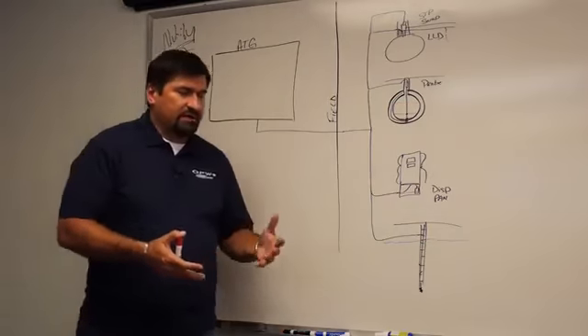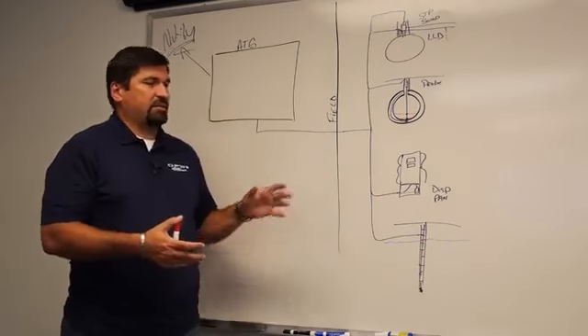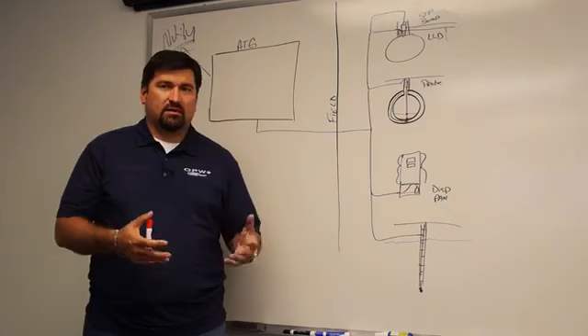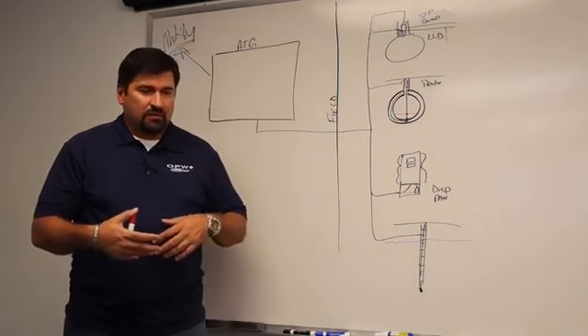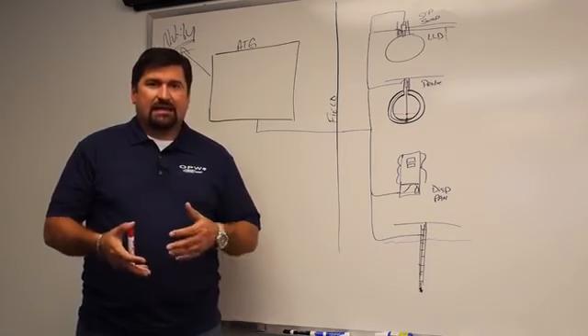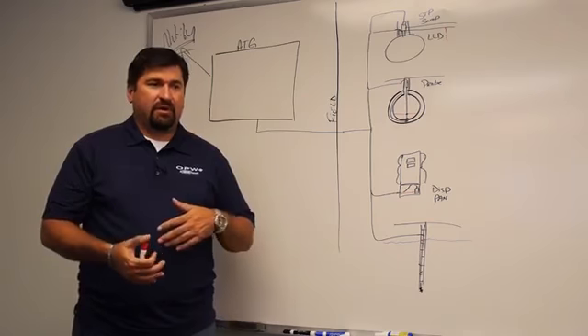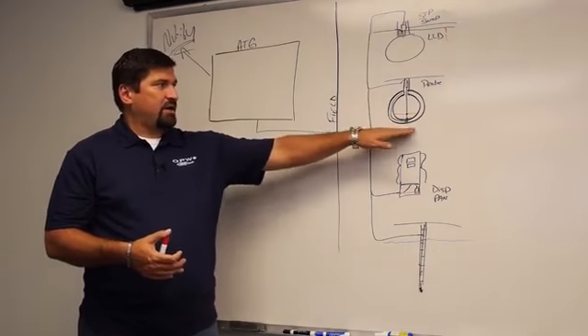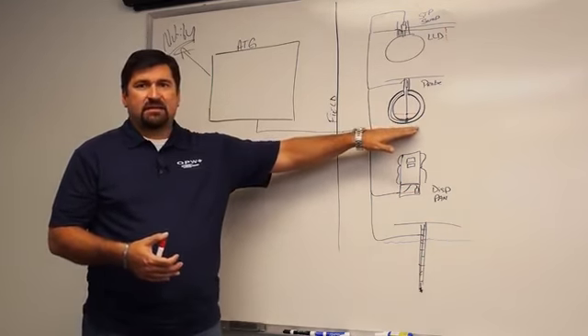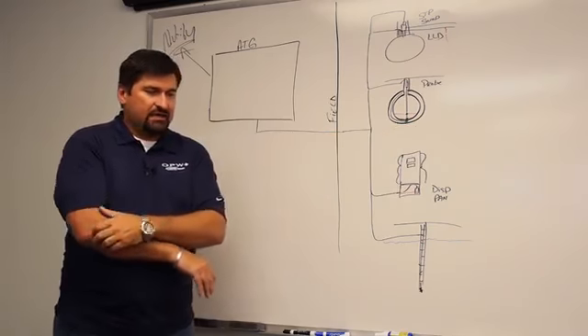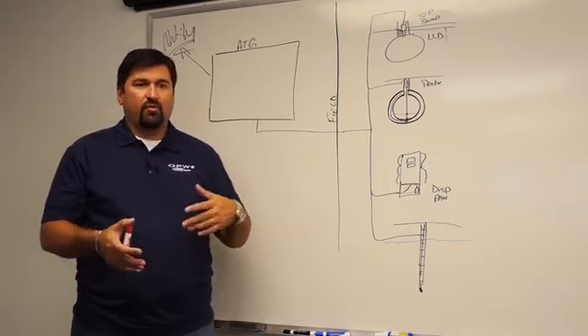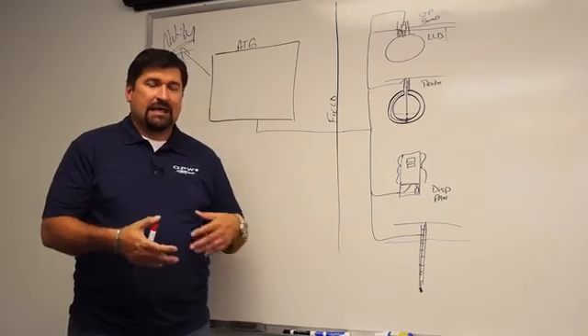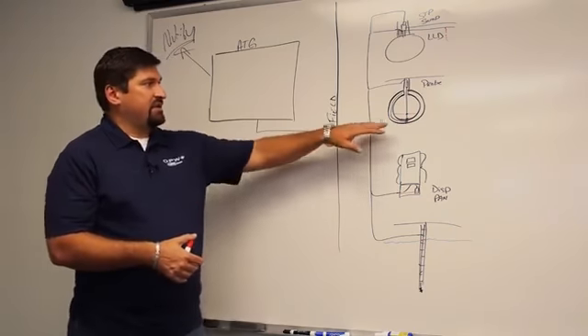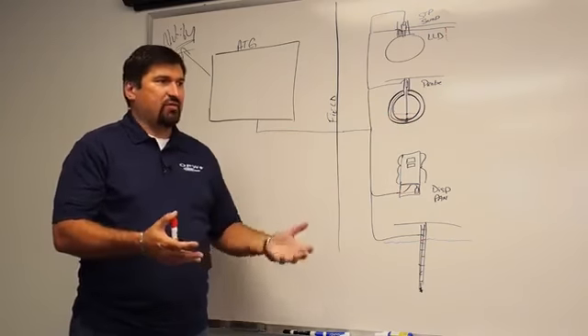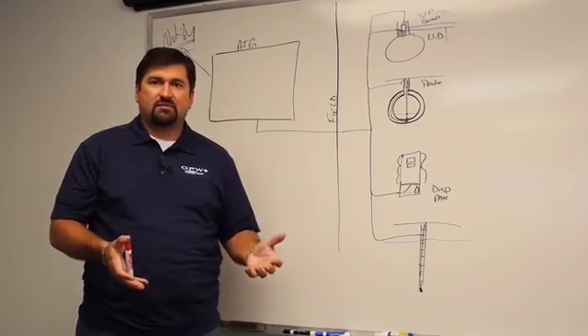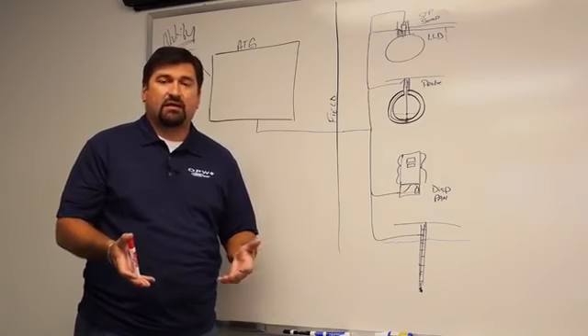Okay, so when we start looking at the ATG in general, we talked about the monitoring, the alerting, and the control. But leaks don't happen at a gas station every day. What happens every day is you're constantly dispensing in and out of this tank. So it's designed to let you know when you reach the point within the tank that you need to get a delivery. These thresholds can be programmed. Let's say you want to know when you get down to 1,000 gallons within the tank, or 10 inches of product left in the tank.